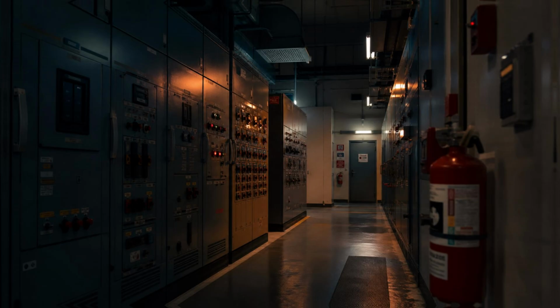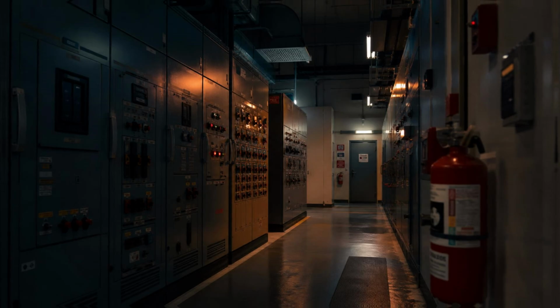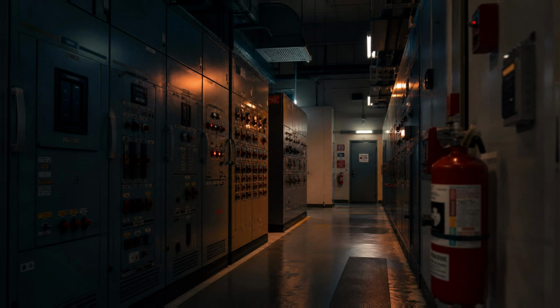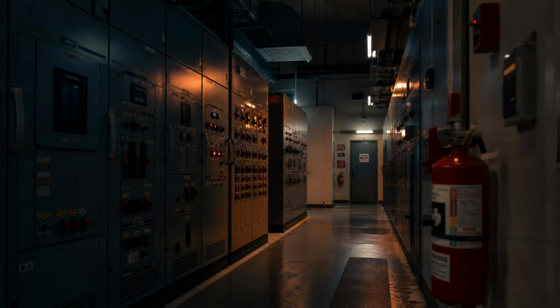A load test, more demanding, more informative, and more satisfying in its thoroughness, connects the generator to either the actual building loads or to a portable load bank, and runs the machine under something closer to real conditions. The load bank, if used, is a device that draws a controlled and measurable amount of power from the generator, simulating the kind of demand the generator would face in an actual outage. Running under load stresses the fuel system, the cooling system, the voltage regulation, and the engine itself in ways that a no-load exercise does not.